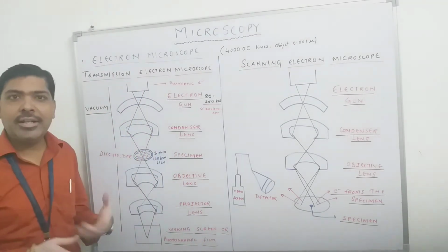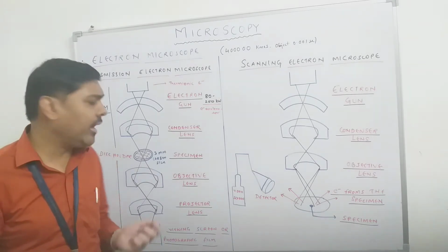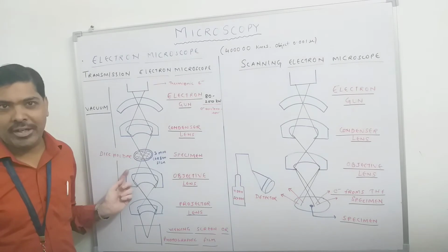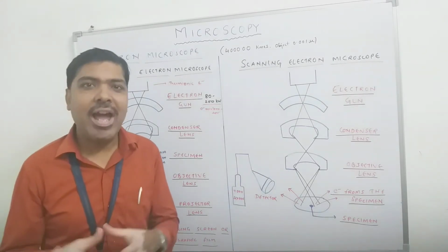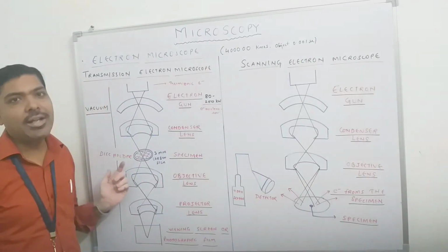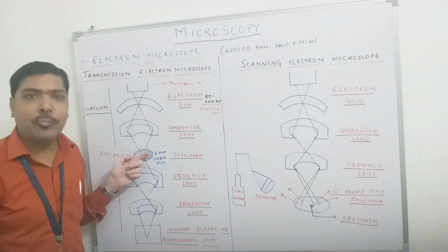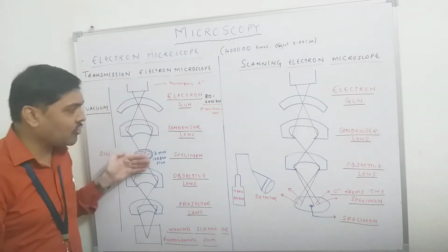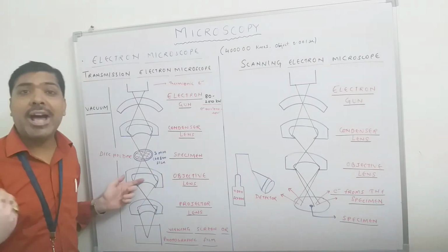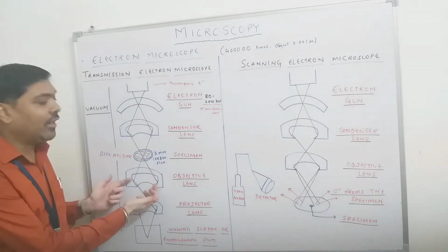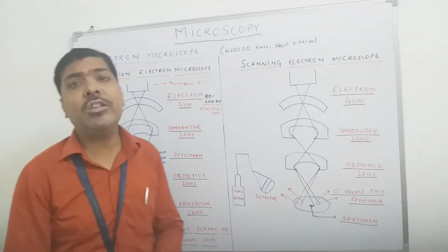a specialized specimen holder available, and inside that holder we have to put this disc holder. Okay, now this disc holder has a mesh-like structure, and the diameter of this holder is around 3 millimeters. Whatever sample we have put in the specimen holder, the electrons from the condenser lens will pass through that holder and be directed towards the objective lens, and that objective lens magnifies the image.